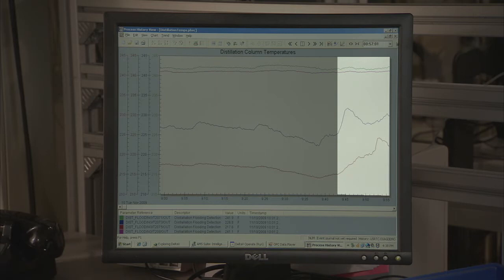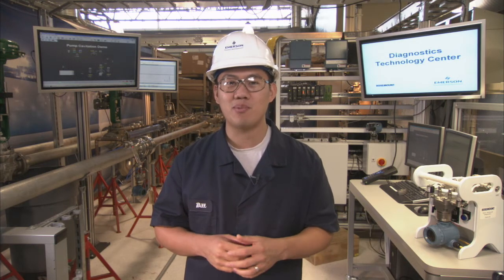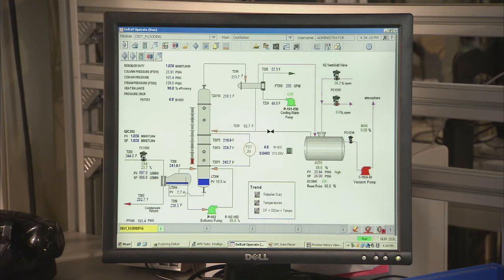The 3051S is not only a high-performance pressure transmitter, but it can also measure and perform statistical process calculations based on the process noise. As the column begins to flood, there is a step change in this process variability. This changes standard deviation and delivers an early warning of impending flooding condition. Here, we can see that the 3051S has triggered an alert notifying the operator that flooding may have started.